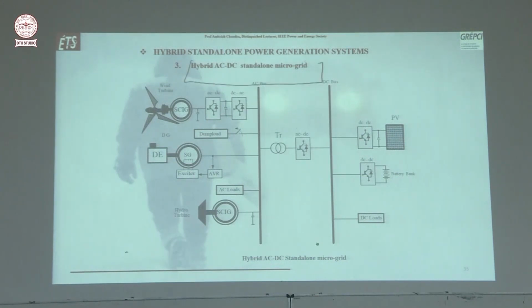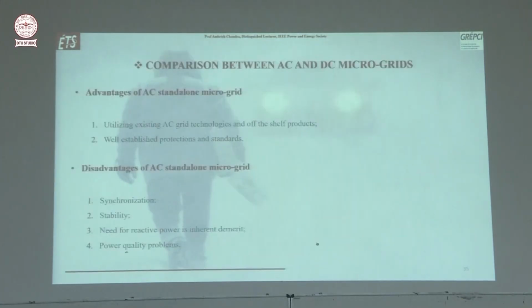Then there are many hybrid AC-DC standalone microgrids, where you have both an AC bus and a DC bus. Generators and loads that are DC in nature connect to the DC bus, and those that are AC in nature connect to the AC bus. Between the AC and DC bus you have a bi-directional converter, so power can flow in either direction depending on the situation. That's how you can save a lot of money.